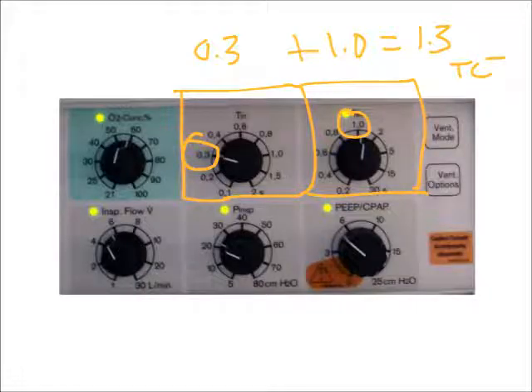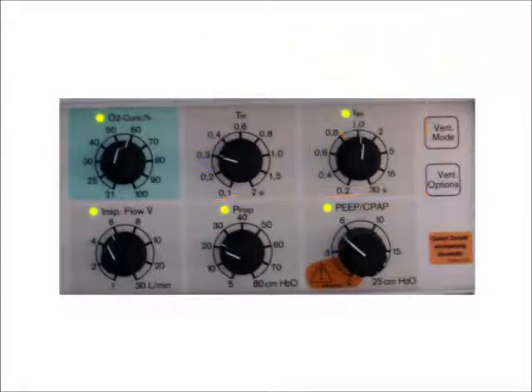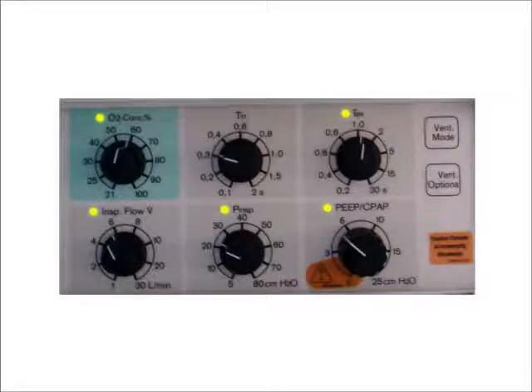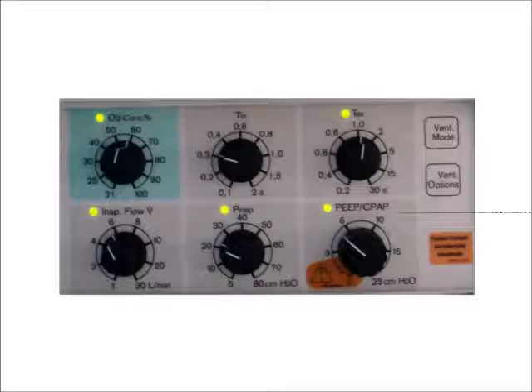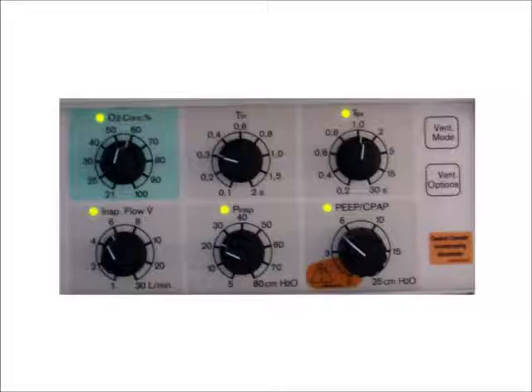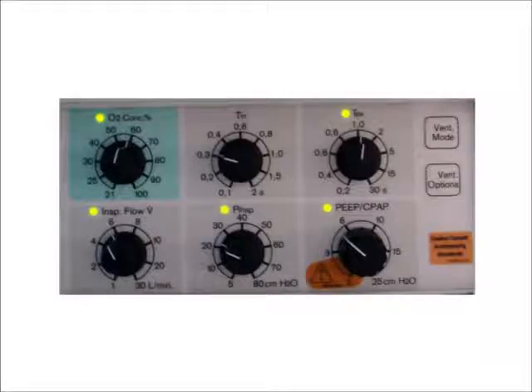Some ventilators still today actually set an inspiratory and expiratory time, and I really don't know a frequency, so I have to calculate my frequency based on that. More people are more focused on setting a frequency than setting an expiratory time. It's a good way to figure out frequency, but on the Babylog it has a screen that shows what the frequency is, so you don't have to mathematically figure it out.